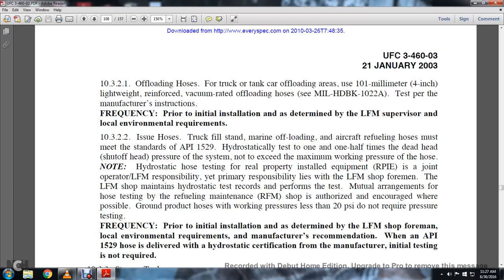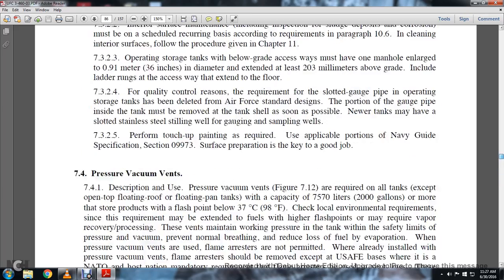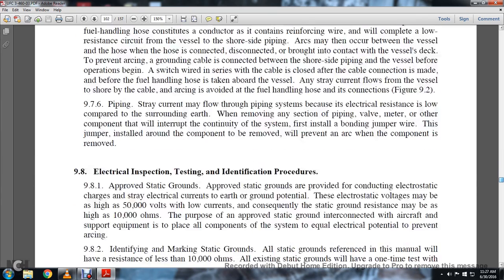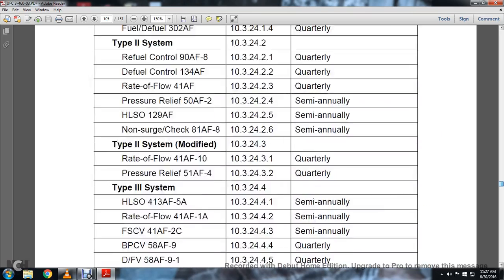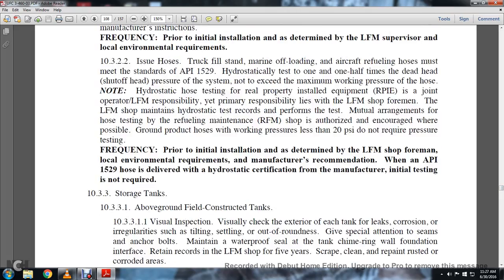Mutual agreements with the refueling maintenance or recurring fuel maintenance shop for hose testing are authorized. Encourage where possible. Ground product hoses with working pressure less than 20 psi do not require pressure testing. Frequency prior to initial installation is determined by the LFM shop foreman, local environmental requirements and the manufacturer's recommendation. API 1529 hoses are delivered with hydrostatic certification from the manufacturer. Initial testing is not required.